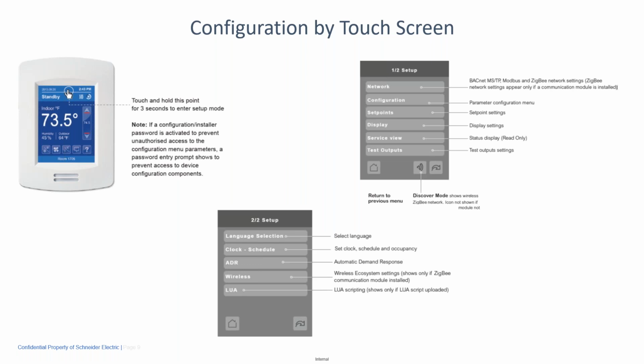The test output screen allows you to toggle the inputs or outputs on and off, or modulate them from 0 volts to 10 volts DC. So if you wanted to verify that I've wired the device correctly, instead of trying to fake out the controller, raise up the set point so that the heat comes on, or lower the set point so the cool comes on, you can just go to the test output screen and say, I'm turning on heat or modulating heat. I'm turning the cooling on and off. I'm turning the fan on, low, medium, high speed. Yes, I've configured those all correctly. So it's a great opportunity for any sort of commissioning or checkout procedure to verify that your electrician has wired them correctly or that they're operating correctly, from the get-go.